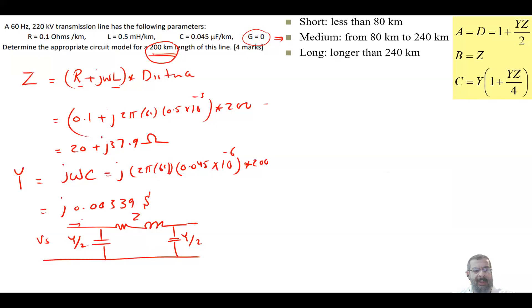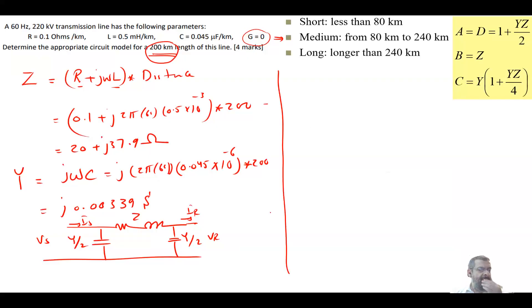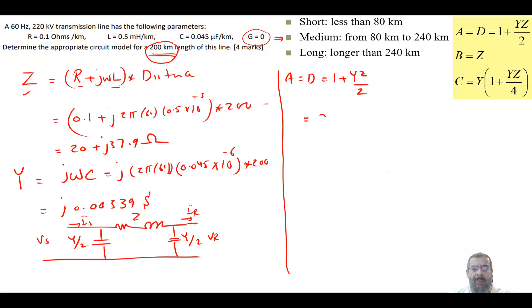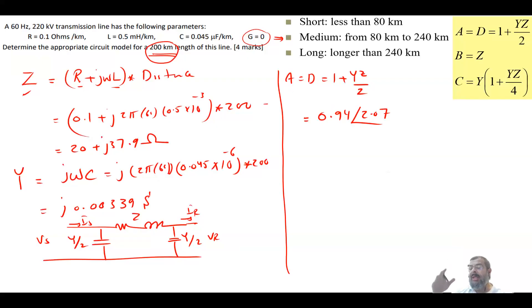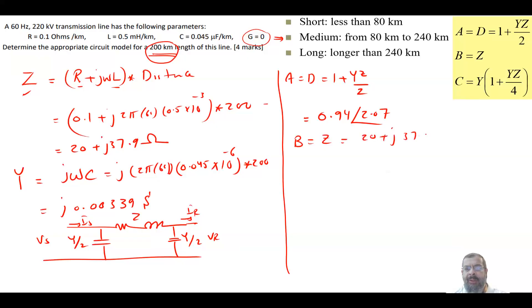In the pi model, Vs and Is are at the sending end, and Vr and Ir are at the receiving end. Applying the ABCD parameter formulas: A = D = 1 + YZ/2. With the values we calculated, this gives A = 0.94∠2.07°. Note that for a short transmission line A and D equal 1, so as the line gets longer, A and D decrease. B equals Z = 20 + j37.9 ohms, same as for the short line.